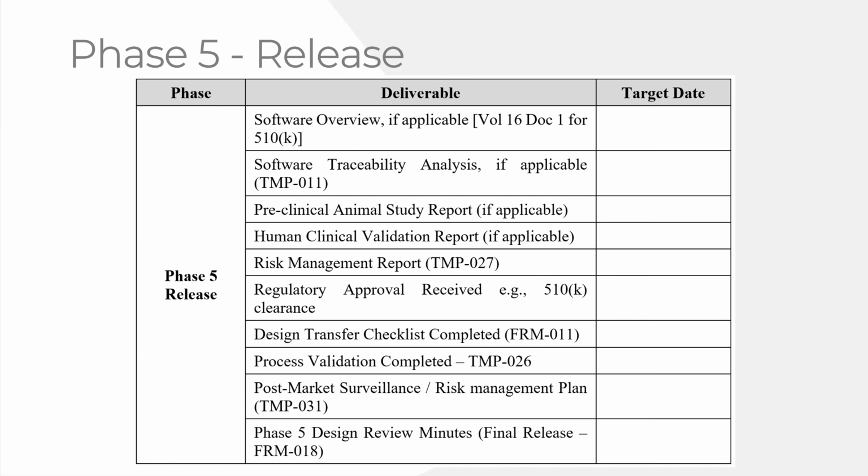V&V testing. If that's the case, you're going to need this software overview because it's for a 510K, and you're going to need the traceability analysis. They want that software traceability in the 510K as well. It's one of those 11 documents that are listed here.